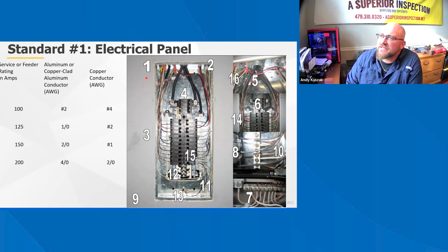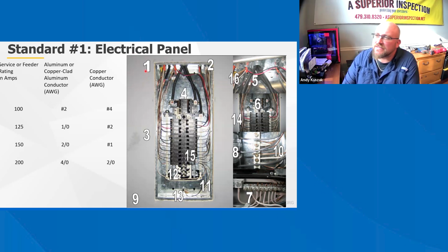Service. Service is a general term used to refer to all of the service conductors and equipment for delivering electricity from the utility company to the wiring system of the building served. The service begins at the load end of the service drop or lateral and ends at the enclosure that houses the main disconnecting means. It is typically referred to as the main panel. The first point of disconnect for the conductors from the utility company is the service or the main panel.